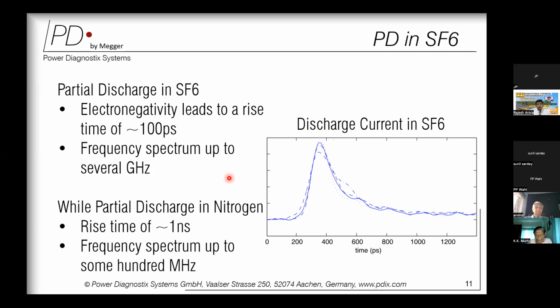Now, if we take the same partial discharge, if it is happening in nitrogen or any other gas, the typical rise times could be of the order of nanoseconds, and it will generate a frequency spectrum only up to a few megahertz. And that is why it is a medium frequency range, not an ultra high frequency range. So maybe it is the discharge which is happening in the respective insulating material that will result in a spectrum leading to a particular frequency band. So every partial discharge measurement in the UHF band or in the medium frequency band needs a different type of sensor technology and a different type of measurement mechanism.